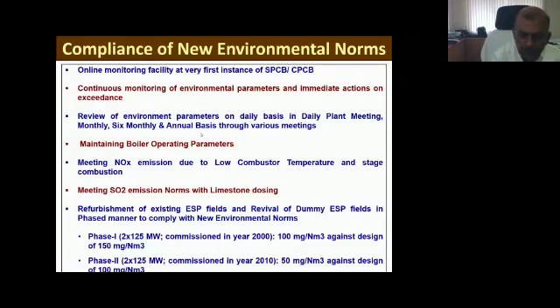Refurbishment of existing ESP fields - we have almost 60 ESP fields across all 4 units. We have retrofitted almost 50%, about 30 ESP fields, and the balance is in process. In the design itself, we kept provision for dummy fields in both phase 1 and phase 2. Phase 1 has 7 dummy fields at the end, but in phase 2 the first field itself is a dummy field, which we have now revived.